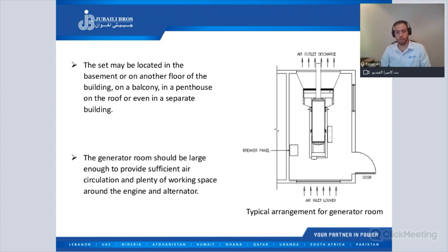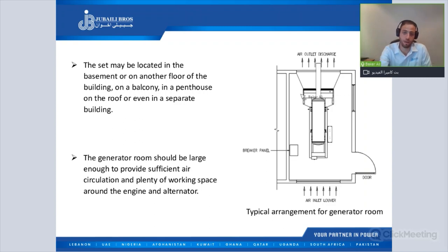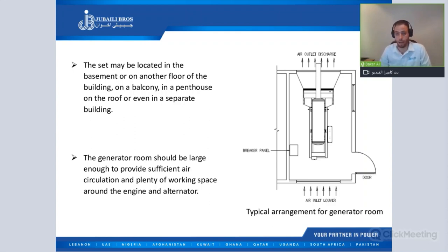When installing the generator in a room, care must be taken to keep easy access to provide proper access for maintenance and general repairs. We have to keep enough space around the generator for easy access for maintenance and repair. We must have easy access to perform generator general services like changing oil and filters, filling oil, filling coolant, and removing and installing the main components of the engine and alternator, like cylinder heads, starter motor, and DC alternator.